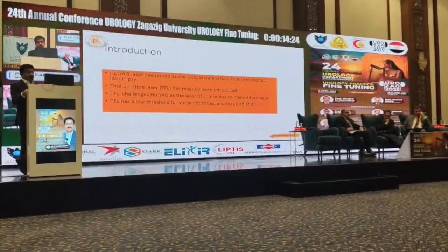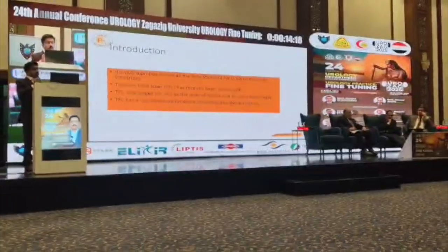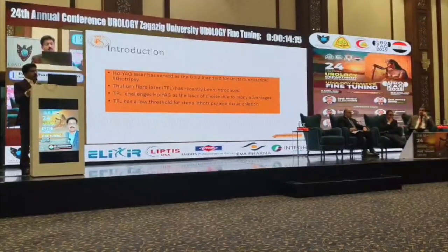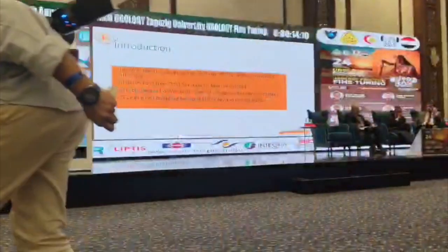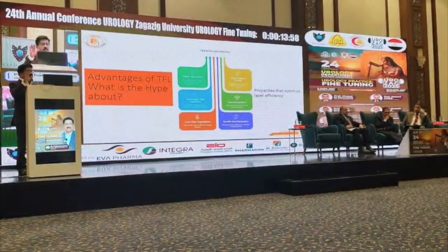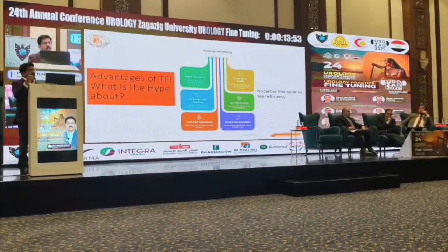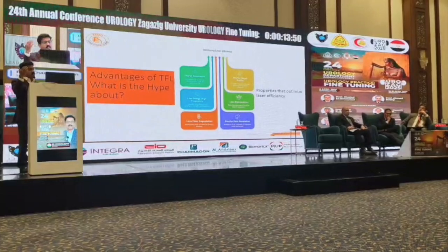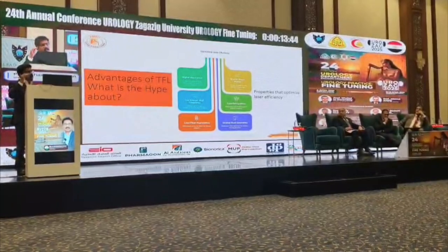You have seen Holmium laser for the last 10 to 20 years. Now, in the last 5 to 10 years, Thulium fiber laser is coming. This is different from Thulium laser. For both stone and prostate, this Thulium fiber laser is used. The main advantage is in stone, which I will focus my talk on. It absorbs by water and bubbles are produced much faster than Holmium laser. It has very high frequency and very low energy.